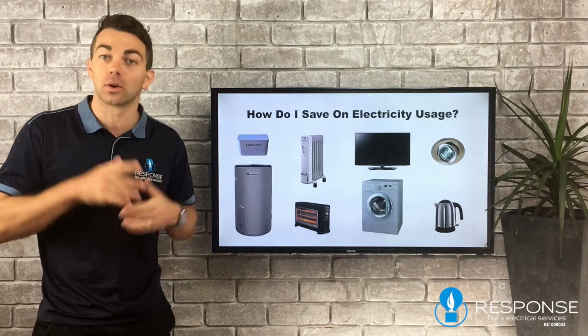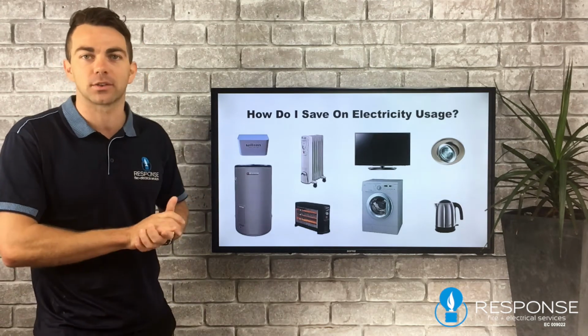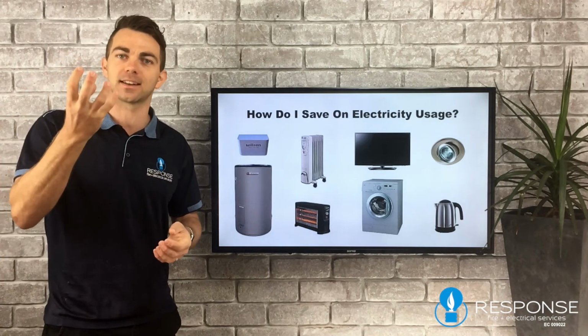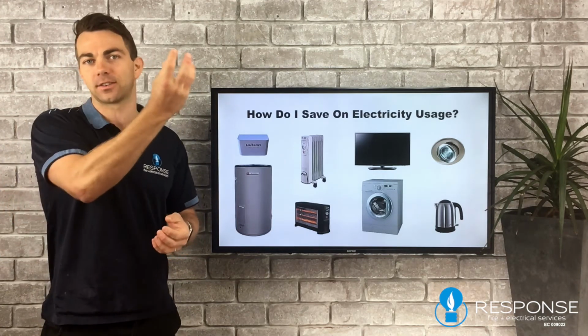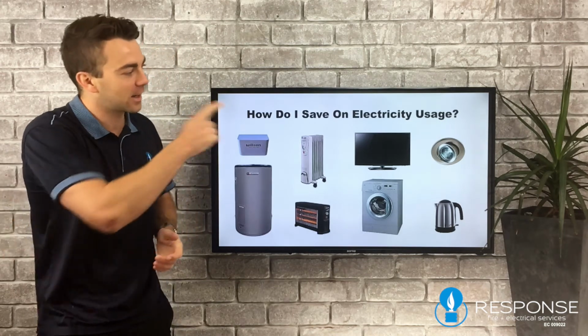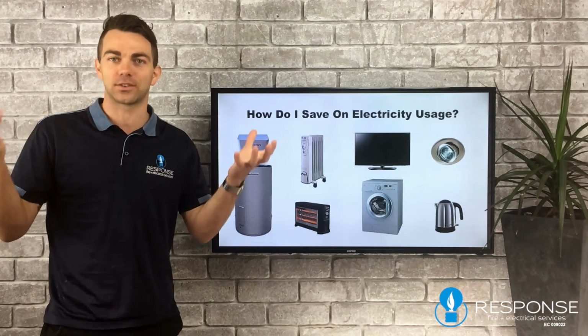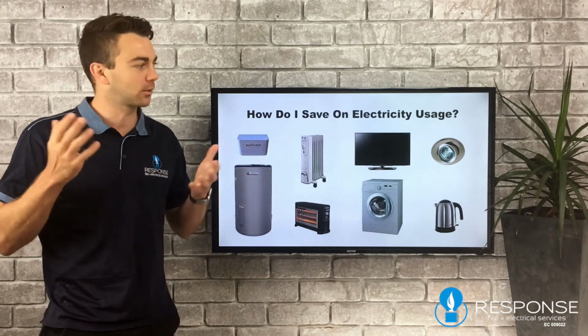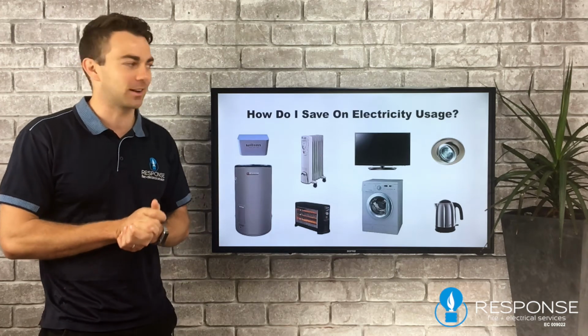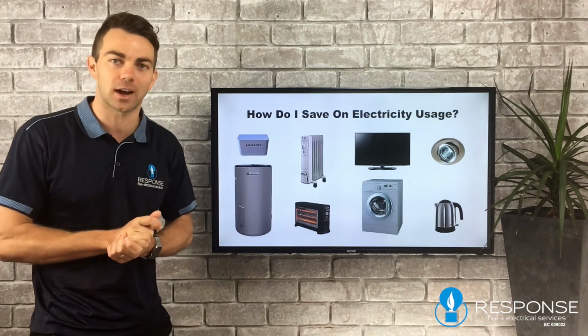Halogen downlights, or just lighting in general. The thing about halogen downlights, they draw about 50 watts each. Remember, 60 watt incandescent globes that we used to have in the center of one fitting in the center of each room. Now you get your halogen downlights, and there's about 4 to 6 in each room. So that's 300 watts, and you usually have them on all day and night. So they're going to be using a lot of current.